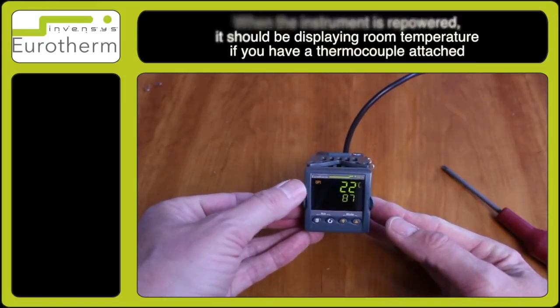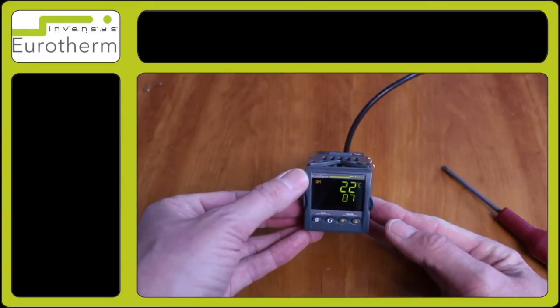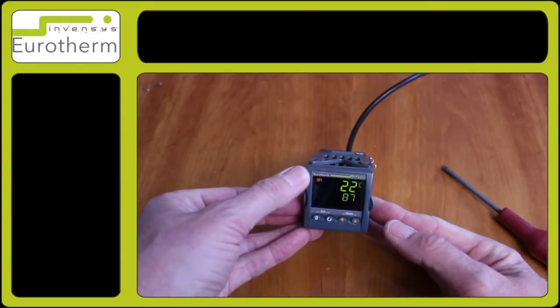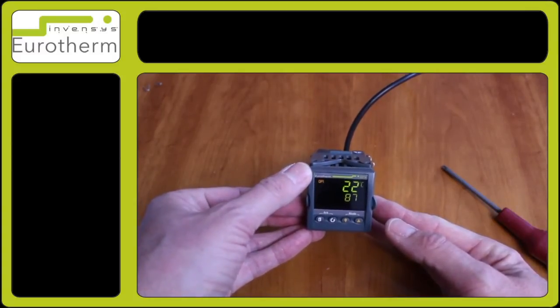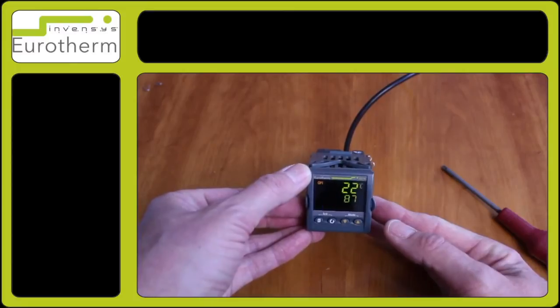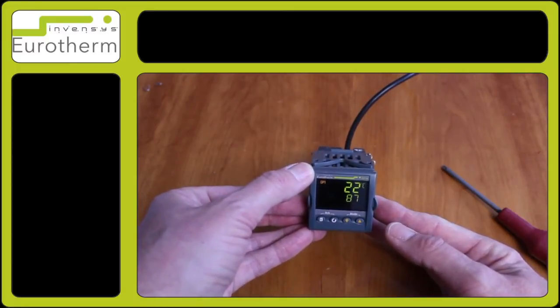And this is a simple way to test to make sure that the input appears to be working okay. If this is the observation you have on your instrument then you probably have a thermocouple problem. An open circuit thermocouple or one that needs replacing.